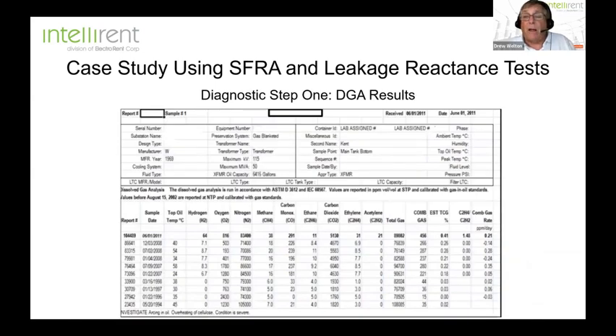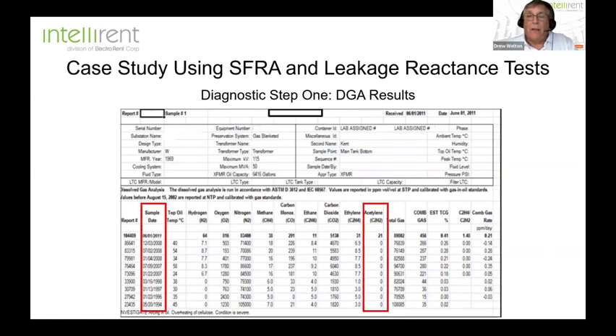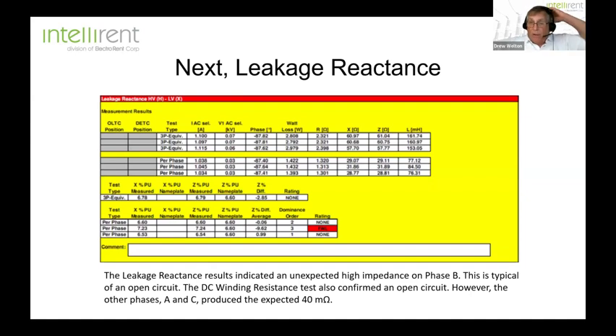Well, then they looked at the dissolved gas analysis. And the one thing you'll notice here is that, of course, this is historical analysis over time. Everything seems to be normal until they get to this test, and you can see the acetylene went from 0 up to 21. And that is a serious indication that we got a problem. Now here's the leakage reactance test results, and you'll see that the three-phase equivalent was well within that 3%, right here. But when we did the per phase, you could see that B phase clearly has an issue.